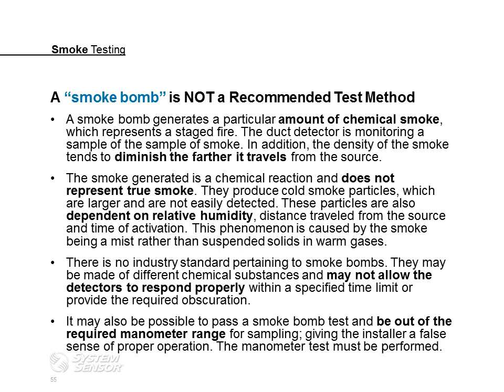And the reason that they're not, and I know they're still widely used in the field, is that a smoke bomb generates a particular amount of chemical smoke, which represents a staged fire. The duct detector is monitoring a sample of the smoke. In addition, the density of the smoke tends to diminish the farther it travels from the source. The smoke generated is a chemical reaction and does not truly represent smoke. Smoke bombs produce cold smoke particles, which are larger and are not easily detected. These particles are also dependent on relative humidity, distance traveled from the source, and time of activation. This phenomenon is caused by the smoke being a mist rather than true smoke, which is suspended solids and warm gases.